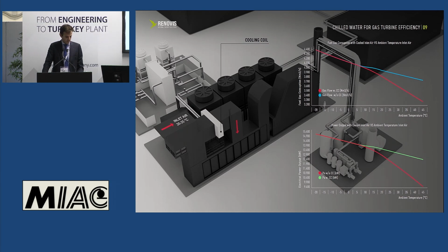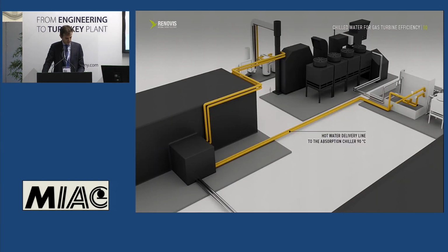We can see, particularly in the diagram below, how the curves of electrical power output from the gas turbine diverge as the temperature of the incoming air increases, depending on the presence or absence of an air pre-cooling system. The green curve, of course, represents the operation of the turbine in presence of a pre-cooling system, and we can see that, on average, the installed system allows us to recover from 1 to 1.5 megawatts of electrical power produced.